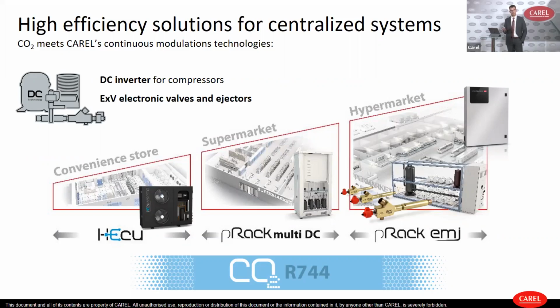These kind of special devices that improve the efficiency of your unit can be fitted in several applications in order to match the cooling capacity requirements of every supermarket size, from the convenience store, so very, very small stores, up to the big hypermarket sizes. So starting from the small sizes, we have HEcu, that is the solution for condensing unit. And by putting more BLDC compressors in parallel, we will see the pRack multi-DC option up to the pRack transcritical for booster system that can manage ejectors and can coordinate the use of an adiabatic cooler called Chill Booster.